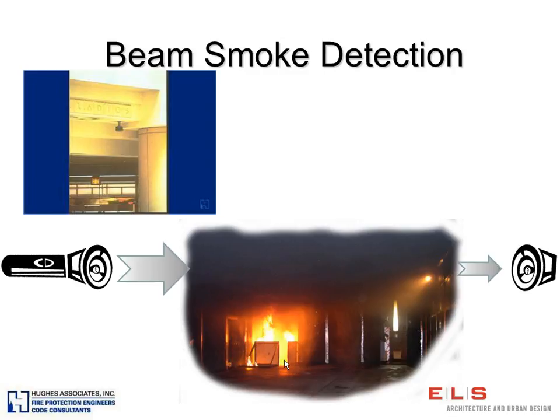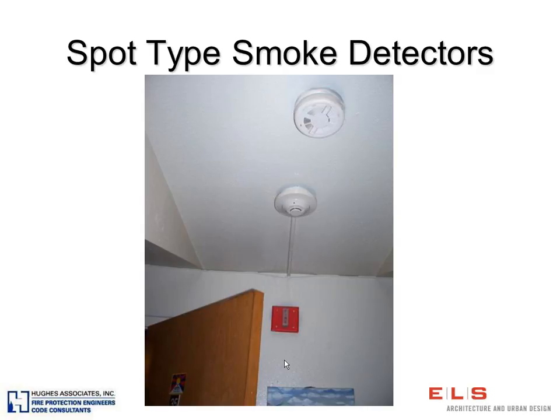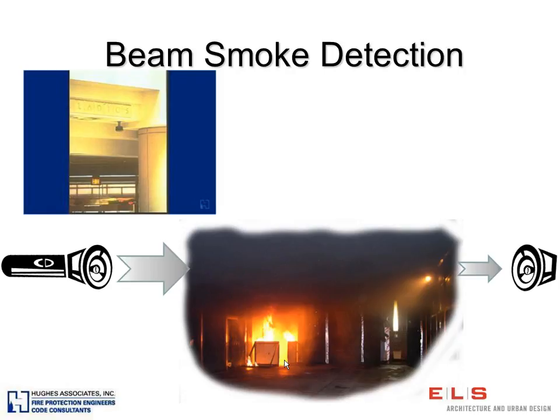Another type of detection that has good application in a historic building would be what's called a projected beam smoke detector. In the previous application of spot type detectors, we typically space them at 30 feet on center, so you would need a smoke detector installed every 900 square feet. Depending on the geometry and configuration of the space, you'd need quite a few of these detectors to protect a large room. One of the benefits of going with a projected beam detector is that you can protect quite a large space with just a single projected beam detector.